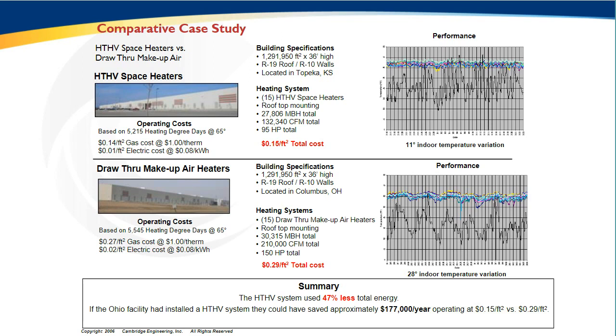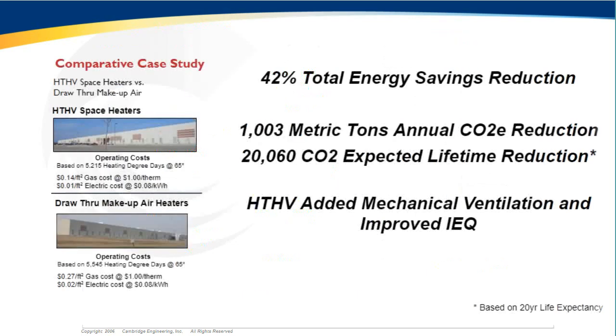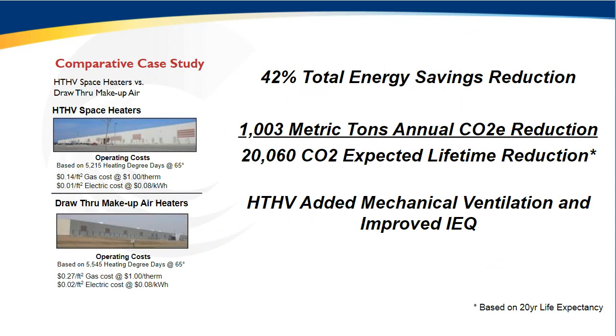Both systems had the same building construction, the same types of usage, the same square footage, the same numbers of units. They both utilized quote-unquote high-efficiency direct-fired combustion. However, the core principles of HTHV with more usable BTUs and more energy transfer per CFM, what they saw was that the HTHV system had 42% total energy savings reduction. So really, this is the proof in the pudding for our thermodynamic lesson. By removing the blower, by increasing the discharge temperature, by deploying HTHV technology compared to low temperature makeup air, massive energy savings and massive emissions reductions. Over 1,000 metric tons of CO2 emissions were reduced in the facility that deployed the HTHV systems over the low temperature draw-through systems.